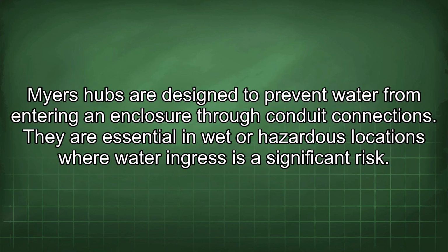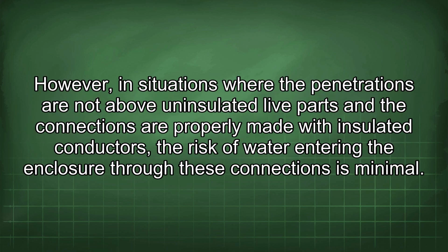Myers hubs are designed to prevent water from entering an enclosure through conduit connections. They are essential in wet or hazardous locations where water ingress is a significant risk. However, in situations where the penetrations are not above uninsulated live parts and the connections are properly made with insulated conductors, the risk of water entering the enclosure through these connections is minimal.